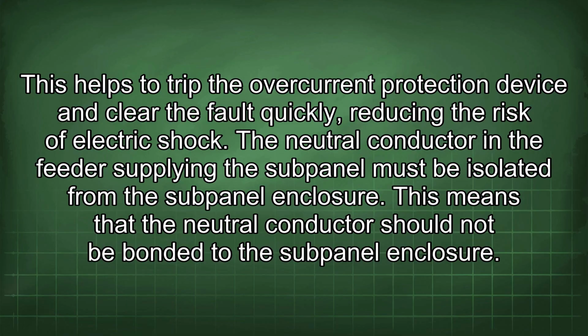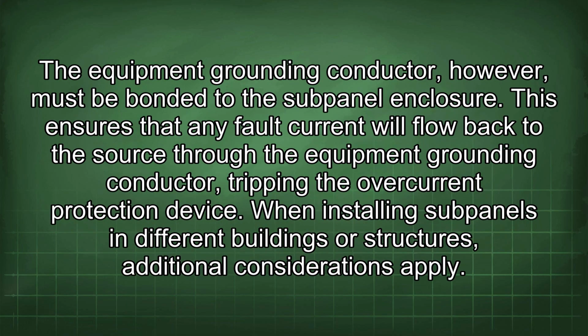The neutral conductor in the feeder supplying the subpanel must be isolated from the subpanel enclosure. This means that the neutral conductors should not be bonded to the subpanel enclosure. The equipment grounding conductor, however, must be bonded to the subpanel enclosure. This ensures that any fault current will flow back to the source through the equipment grounding conductor, tripping the overcurrent protection device. When installing subpanels in different buildings or structures, additional considerations apply.